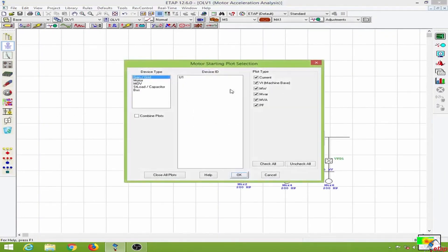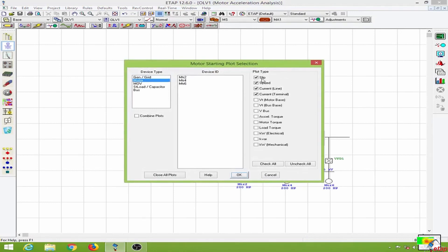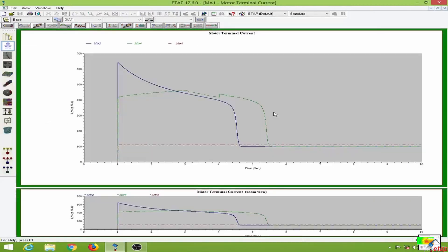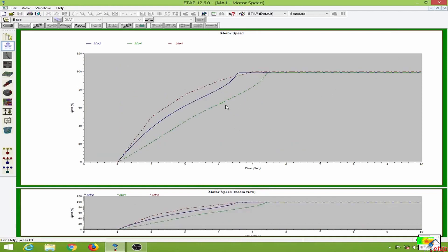Now let us compare the plots. You can see the motor terminal currents — the V/F drive reaches the rated motor terminal current after the starting period but starts very quickly. It does not take the inrush current of motor 2 or motor 4. This is the biggest advantage of the V/F drive: the motor has reached the rated speed faster than the motor having the autotransformer starter and the motor without the starter.